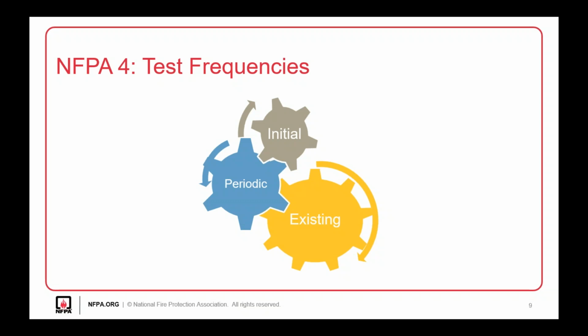Lastly, we have periodic, which is a big deal because how often should we redo integrated system testing? This was a very big discussion amongst the committee. The thought of every 5 years or every 3 years was thrown around, but does that rule really make sense if you're an office building? What if you're a hospital? The systems really play an important role in how often they should be tested, and the testing frequencies identified in your test plan are really up to the integrated testing agent, the owner, and the AHJ.